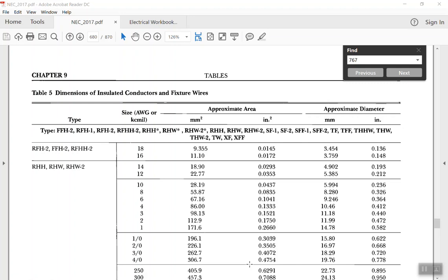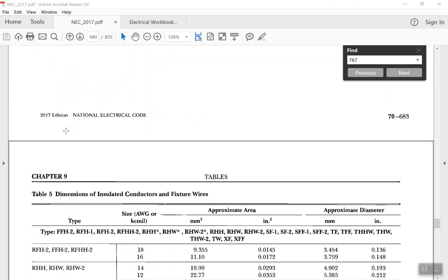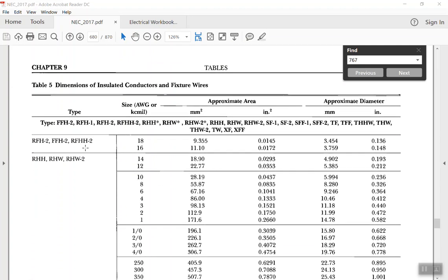We are in section four, conduit fill, for wiring methods and materials. Once again, conduit fill is pretty simple if you use Annex C, but using Chapter 9, Table 5 and Table 4 is a little bit more time consuming. So go ahead and start turning there if you could. Table 5 starts on page 684 in your code books. Let's make sure we understand how to do this. We'll at least do one example, maybe two, and then we've got to move on to some other topics.